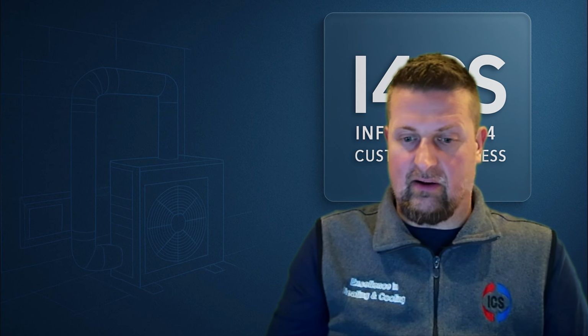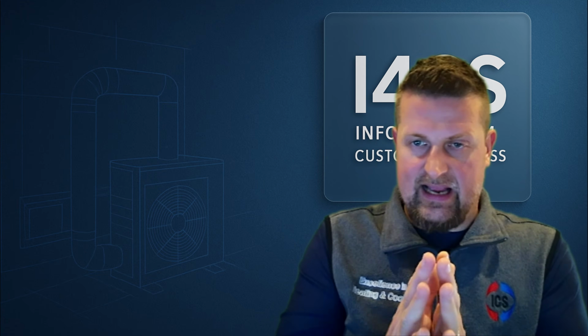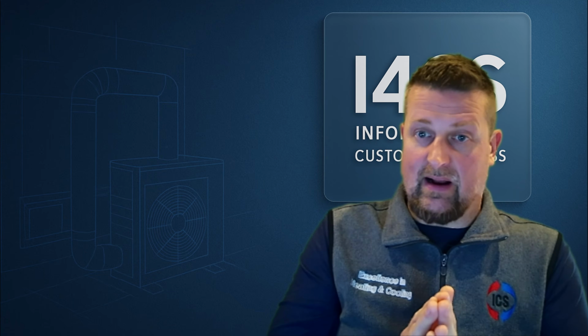The heat exchanger is the component inside the furnace where flue exhaust gases normally do not mix with the air moving past it. But if there are holes in the heat exchanger, you'll get a mixture of house air and exhaust flue air. That could be happening for a while, to different degrees. Obviously, you should not continue to use the furnace in that case.